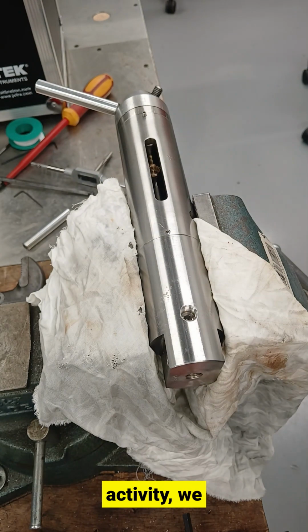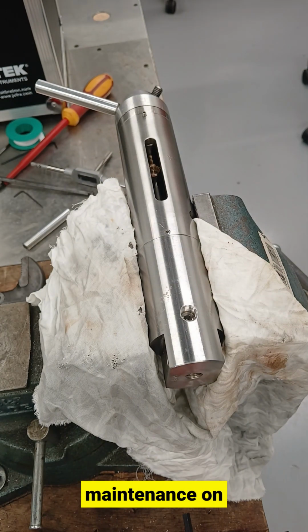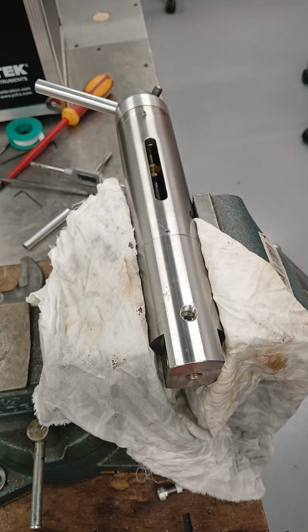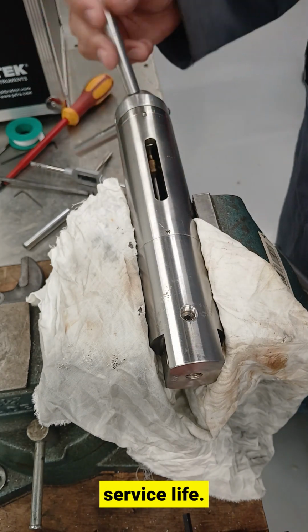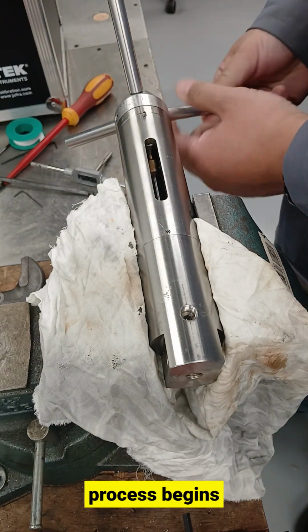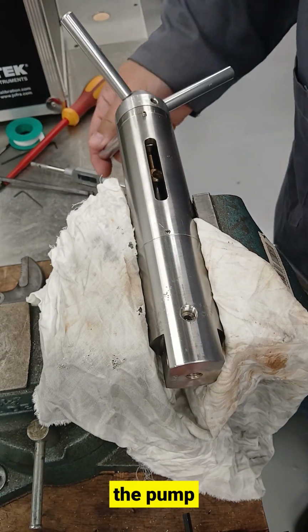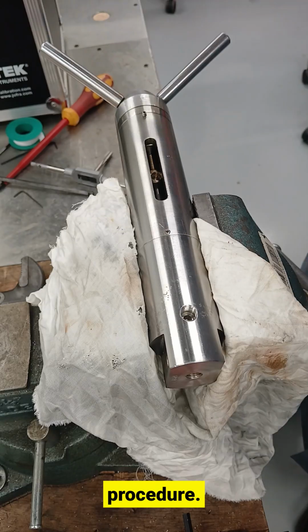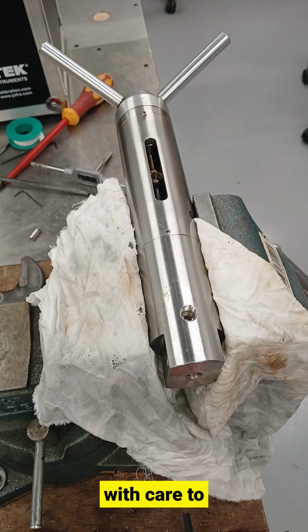In this activity, we are performing preventive maintenance on a manual piston-type pump used in a laboratory testing system. Regular maintenance is essential to ensure reliable operation, accurate pressure generation, and a longer service life. The maintenance process begins by carefully disassembling the pump according to the manufacturer's recommended procedure. Each component is removed with care to prevent damage to the precision-machined parts.